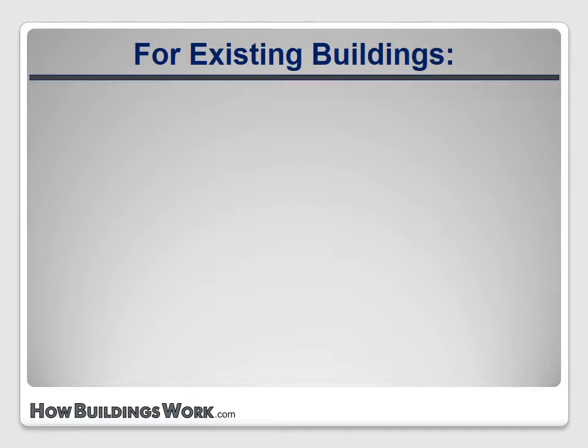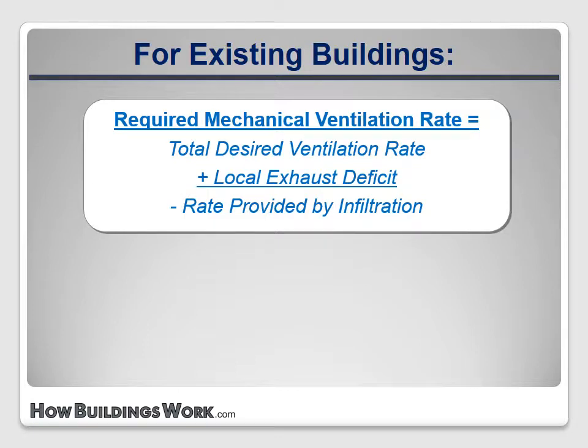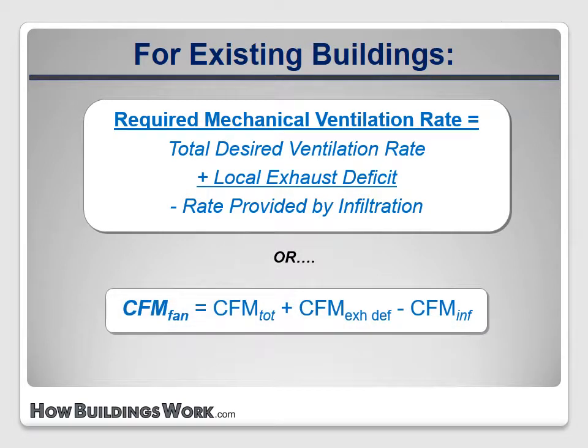This adds another element to the fan sizing calculation. The equation is: the required mechanical ventilation rate equals the total desired ventilation rate plus the local exhaust deficit minus the rate provided by infiltration. We'll abbreviate that to: CFM fan = CFM total + CFM exhaust deficit − CFM infiltration.